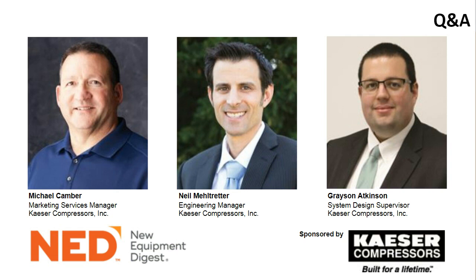Great, thank you. And now a compatibility question. Can Kaeser air treatment components work with any other manufacturer's air compressor system? The short answer is yes. And just like Michael said, it has to do with correction factors as well. But really, a dryer is a dryer. As long as you're considering the main components, which is what's the rated flow, what's the rated pressure, and what are the operating temperatures and ambient conditions, compatibility is really no issue.